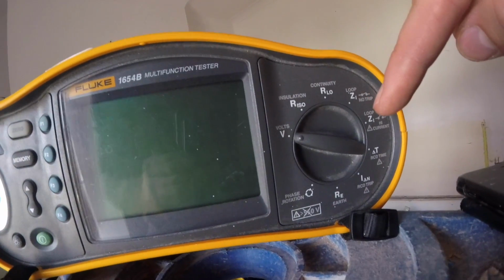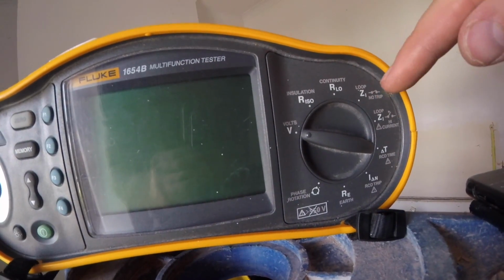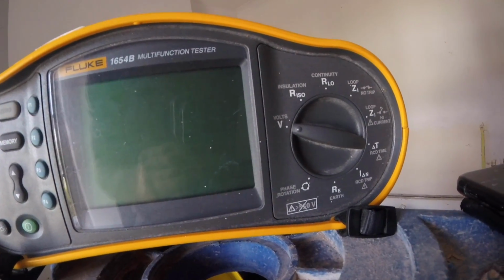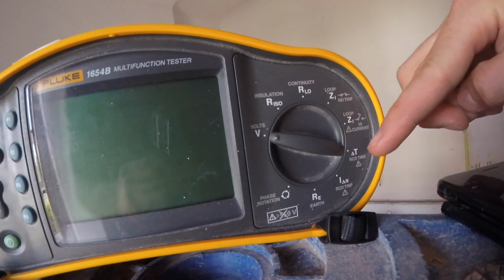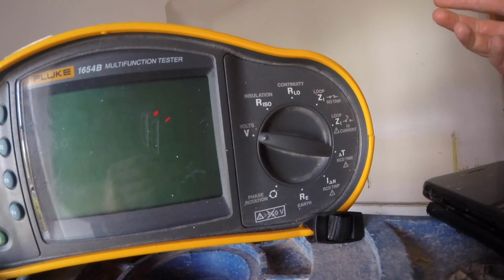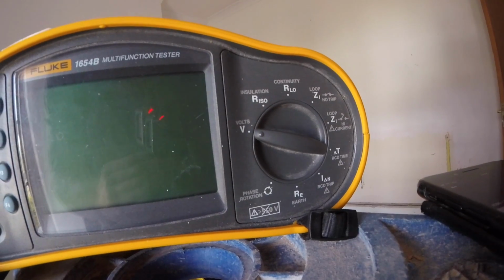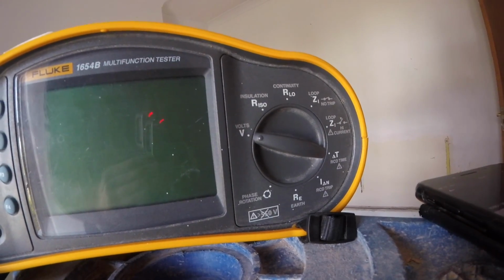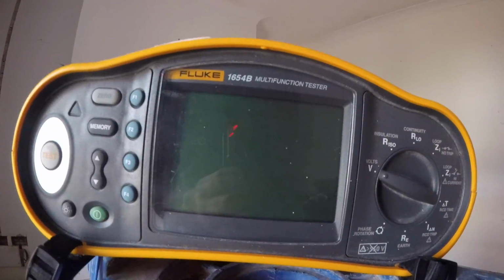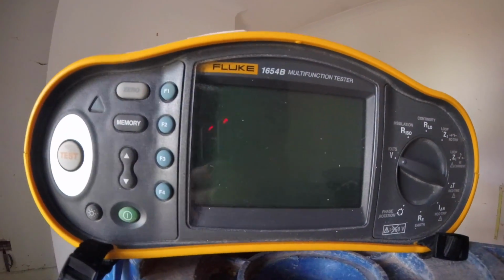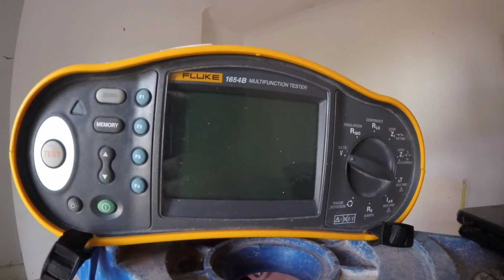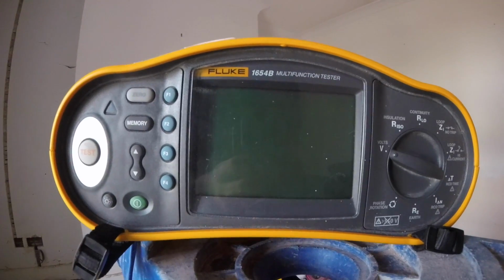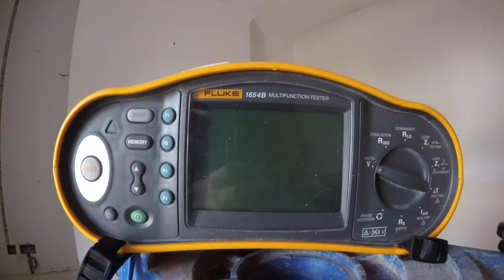You can actually get different meters which will do just single tests, so you can get an earth fault loop impedance tester, an RCD tester, a voltage indicator, an insulation resistance tester. But obviously these are a lot better because it's all in one meter, and it saves carrying around loads of different meters and having to get them all out when you're carrying out tests. So yeah, these are quite beneficial.